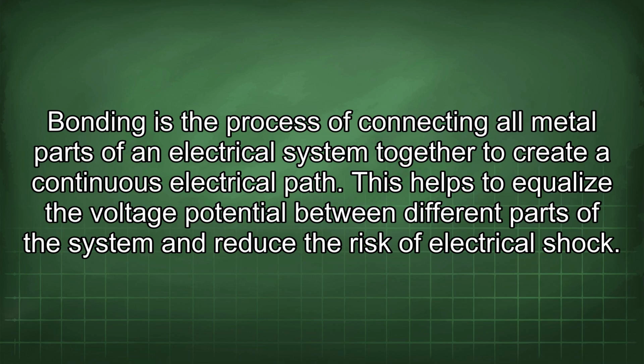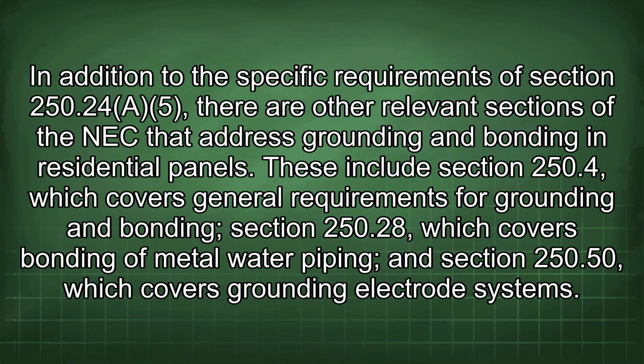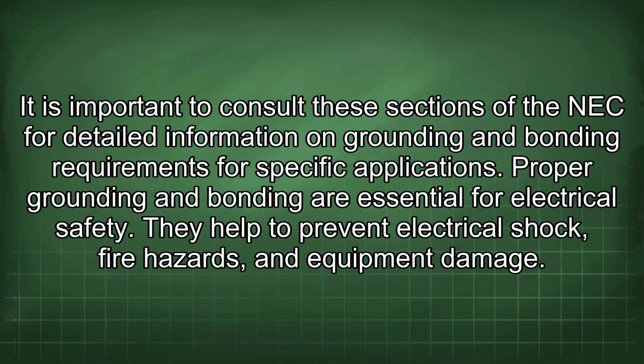In addition to the specific requirements of Section 250.24 of the NEC, there are other relevant sections of the NEC that address grounding and bonding in residential panels. These include Section 250.4, which covers general requirements for grounding and bonding, Section 250.104, which covers bonding of metal water piping, and Section 250.50, which covers grounding electrode systems. It is important to consult these sections of the NEC for detailed information on grounding and bonding requirements for specific applications.